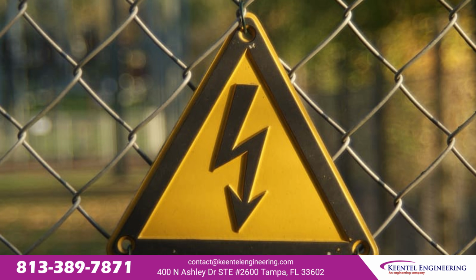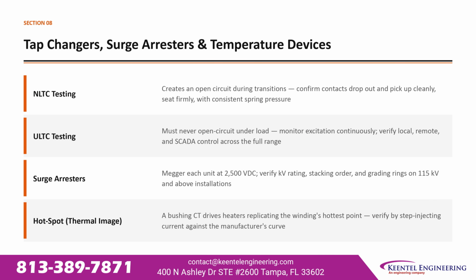any connections. No-load tap changer testing creates an open circuit during transitions. Confirm contacts drop out and pick up cleanly, seating firmly with consistent spring pressure. Underload tap changers must never open circuit under load. Monitor excitation continuously and verify local, remote, and SCADA control across the full range.